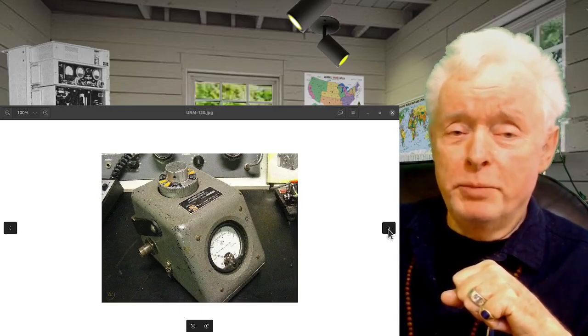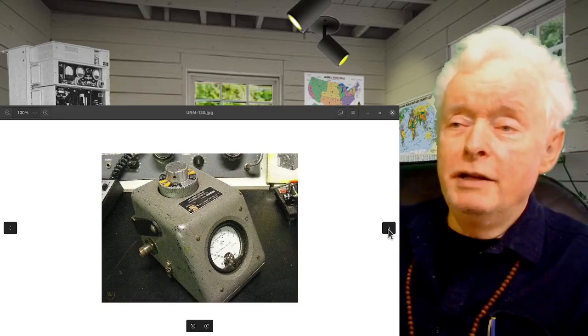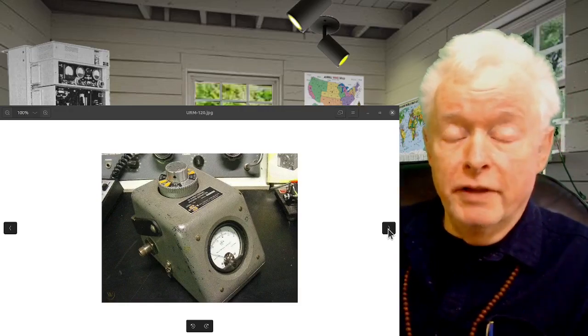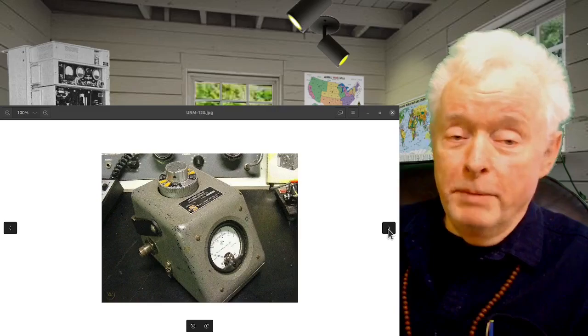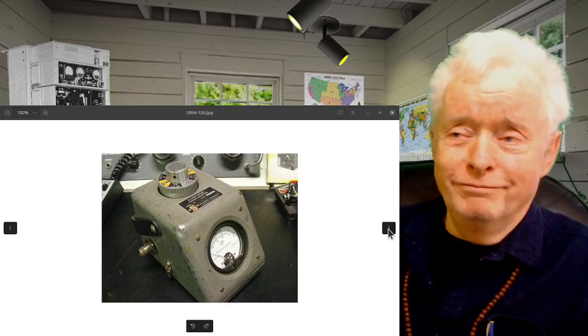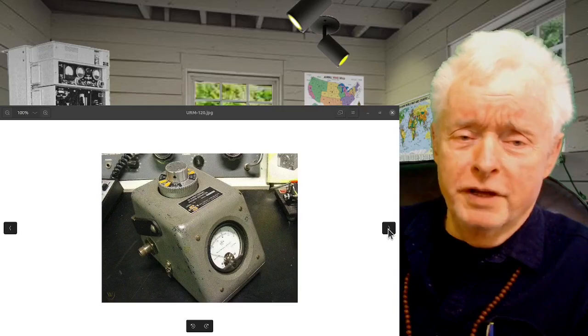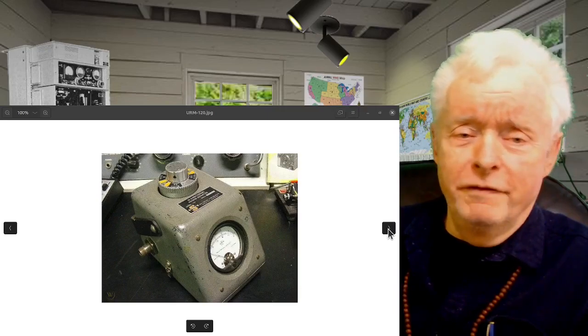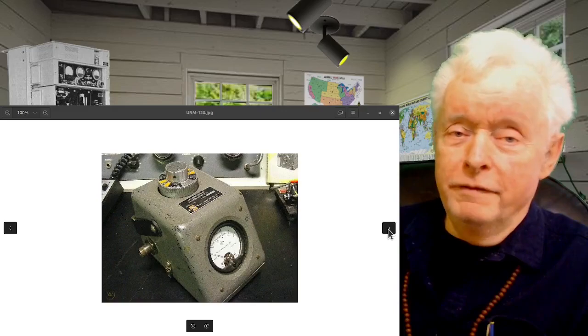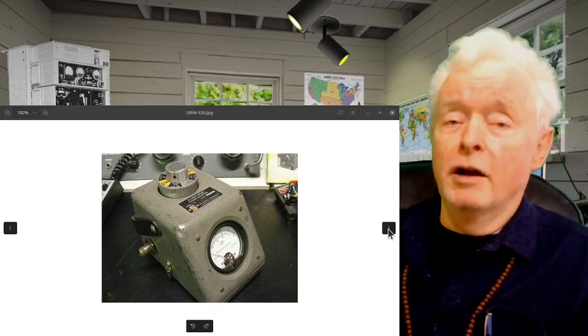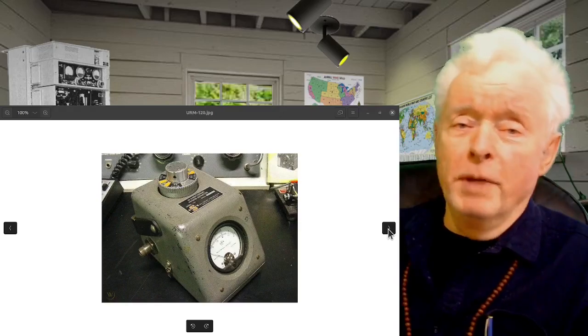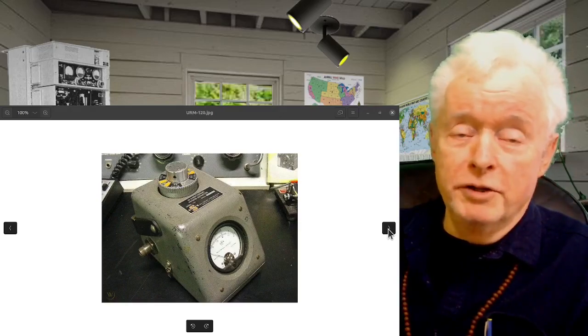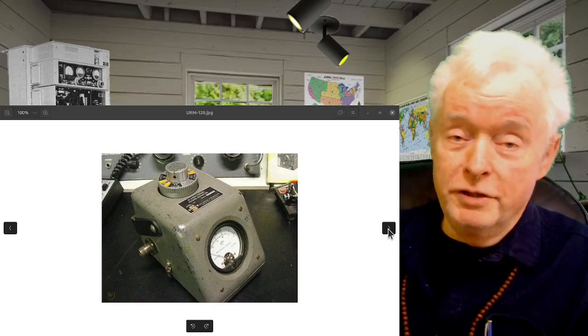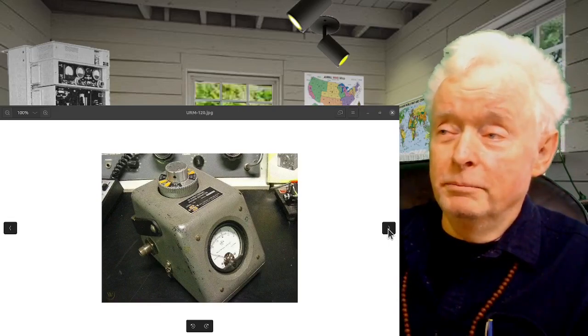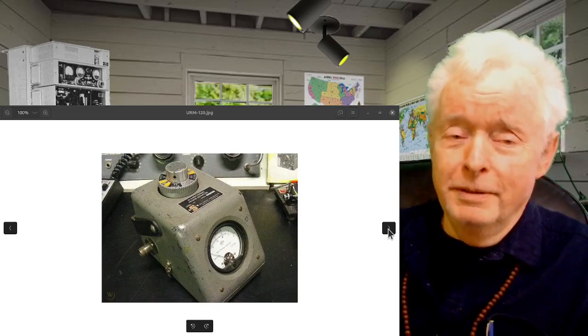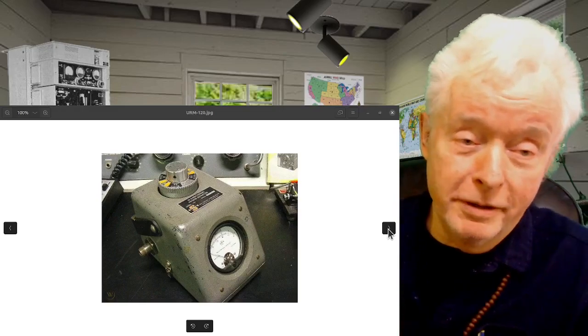The geometries are very simple, but are maintained faithfully through the very large size of the components. It makes it very hard for this to be messed up, short of just breaking the meter itself. It's very, very robust. I've calibrated a lot of these, and this is much better than the Bird meters that you find, and I've calibrated a lot of those too. So you can trust them, but this one is better, much better.